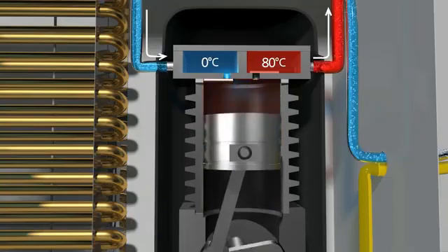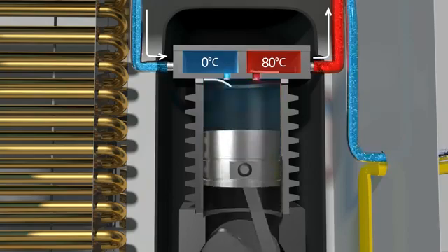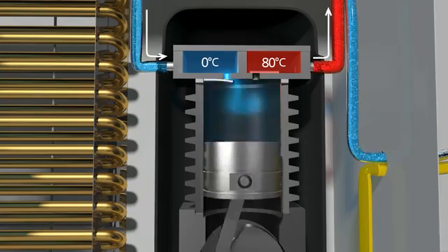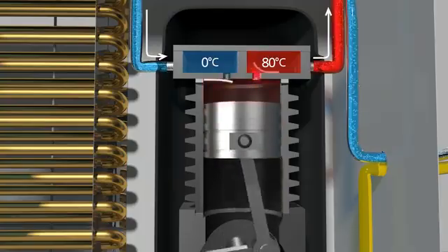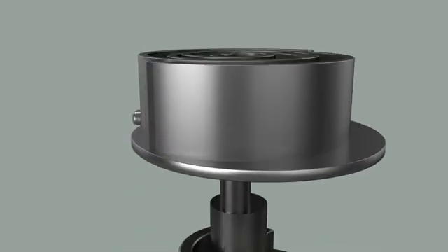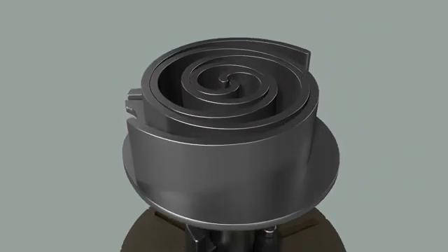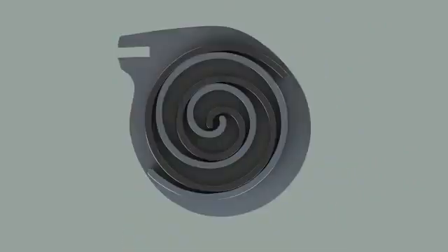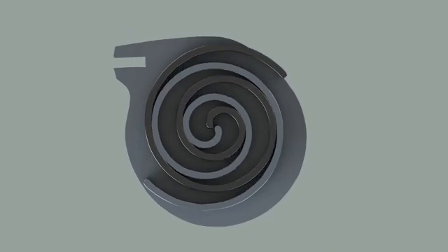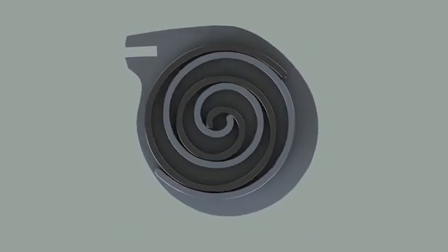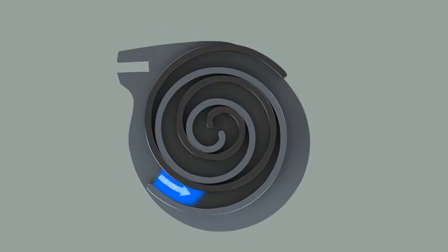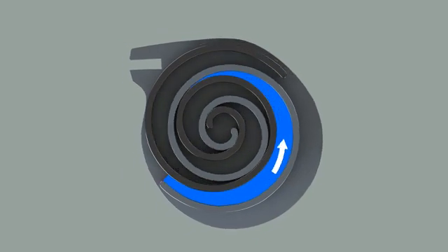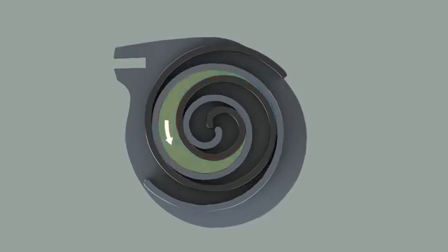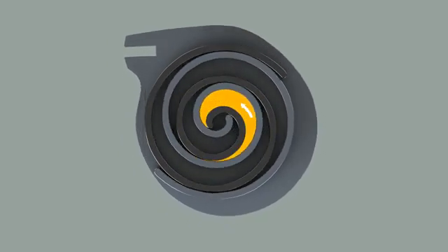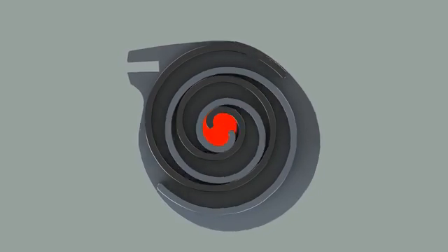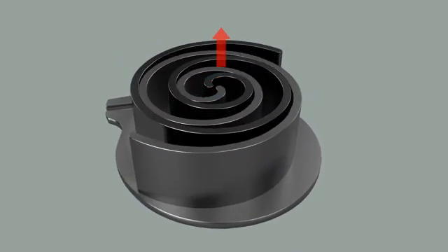Now, coming back to the case of an air conditioner. When gas with low pressure and temperature is pressed by a piston, its pressure rises, and so does its temperature. However, more air conditioners nowadays use a scroll type of compressor rather than a piston type. In a scroll compressor, there are two scrolls of which one is fixed and the other rolls constantly. As more air coming through the entrance gets inside the scroll, space becomes crowded. As there is less space now, gas becomes more compressed and is discharged from the middle of the scroll in a compressed state.